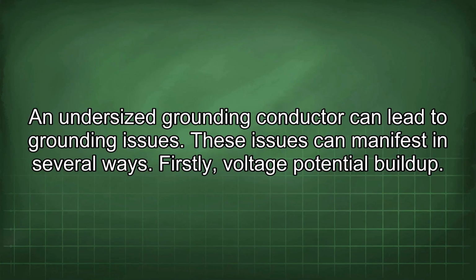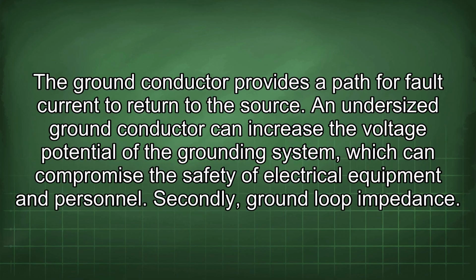An undersized grounding conductor can lead to grounding issues. These issues can manifest in several ways. Firstly, voltage potential buildup. The ground conductor provides a path for fault current to return to the source. An undersized ground conductor can increase the voltage potential of the grounding system, which can compromise the safety of electrical equipment and personnel. Secondly, ground loop impedance.